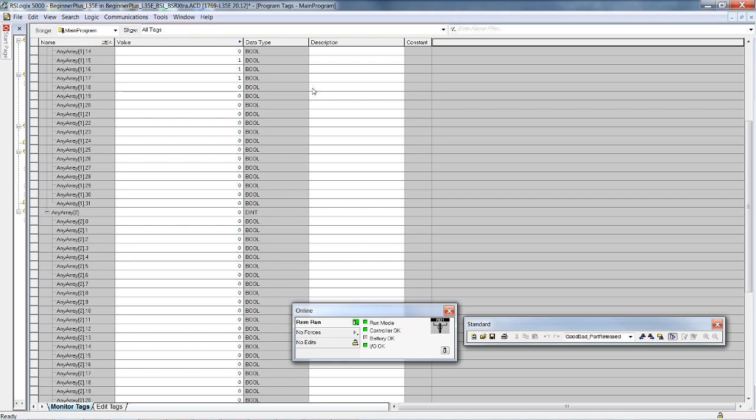Continue then shifting it to the left, which is down, until the leading on bit has shifted into the last bit of element 1, which would be bit 31. It's easy to overshoot. There. Our leading on bit, this on bit right here, is in the last position of that element. But it's not in the last position of our shift field, which is 35 bits. Enable the bit shift left one more time. So watch going from 31 to 32.